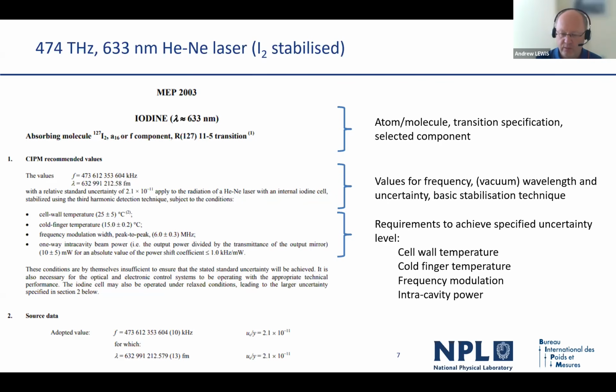But it then tells you what I'm calling critical metadata, which is if you want to achieve all of the things above, then you have to take care about certain operational aspects of your laser, such as the cell wall temperature, the cold finger temperature. And these are really quite critical. If you don't achieve these specifications, then your laser won't be achieving the uncertainty given above, and it won't be the frequency value which the CIPM has recommended. So these are really critical items needed by the person that's doing the experiment, that's doing the calibration of a customer laser using a laser.